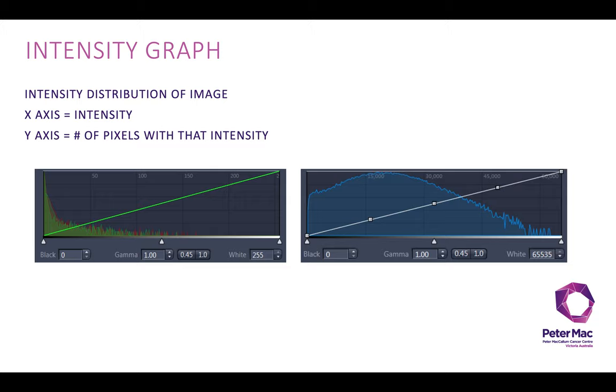On the example on the right-hand side, you can see it's a different bit depth — going from 0 to 65,000. In this case, the signal goes out to about 90% of the dynamic range on the detector, so again not hitting saturation, but using more of the dynamic range.